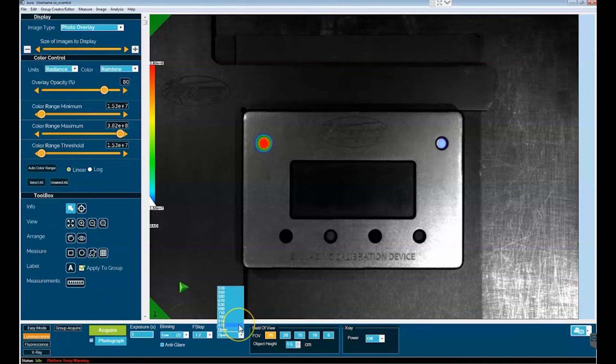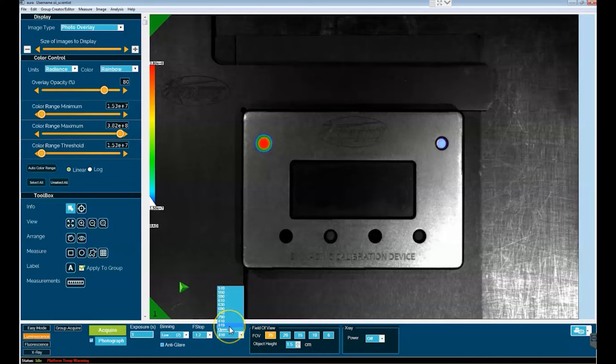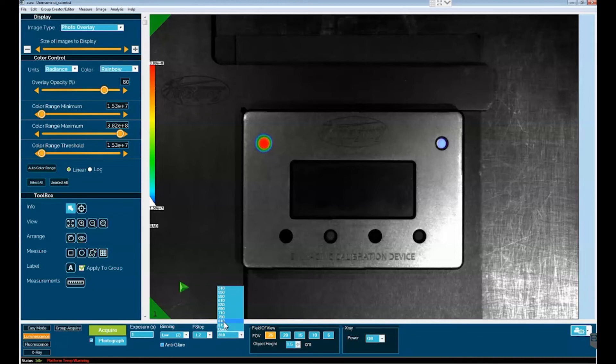With regard to emission, you have the option to select an open pathway to the camera which doesn't use any emission filter. But there are situations in luminescence where you will want to select a specific emission filter, and these are listed here. All of these emission filters are 20 nanometer bandpass filters allowing plus or minus 10 nanometers from the number given here as wavelength that can pass through the filter and go to the camera.